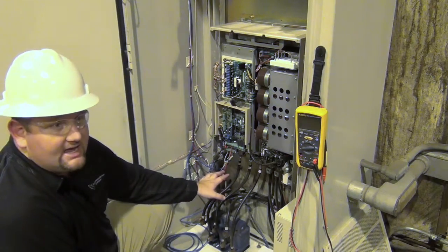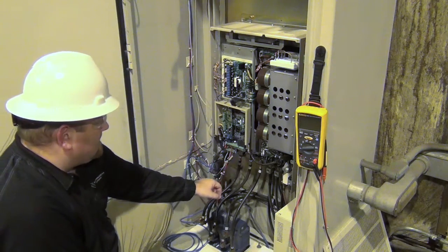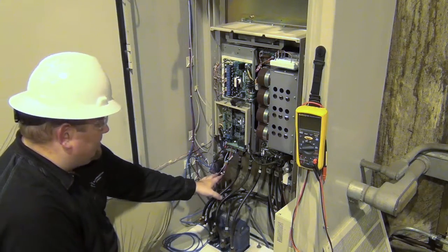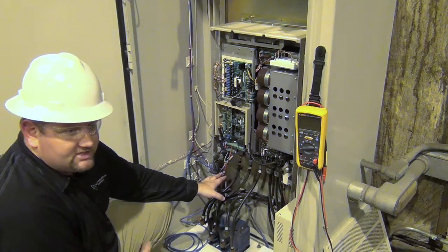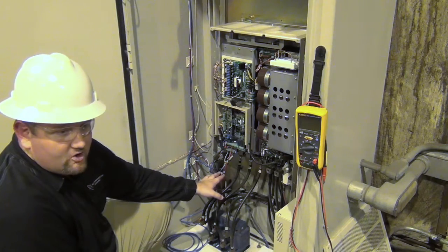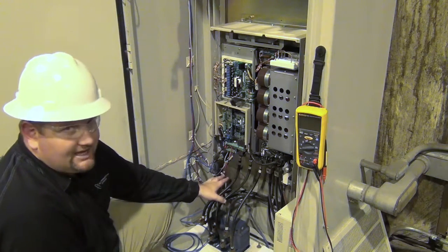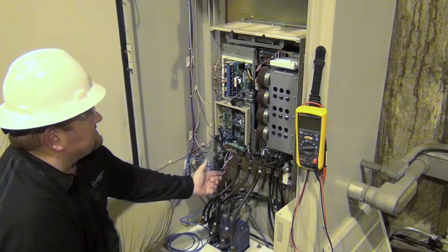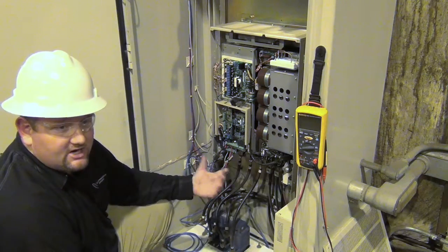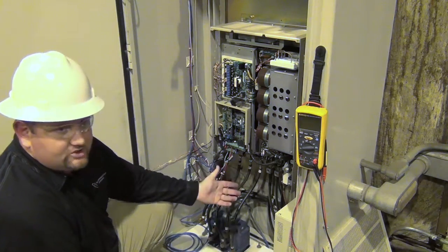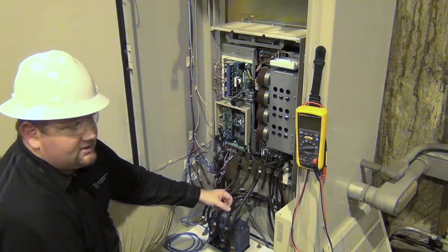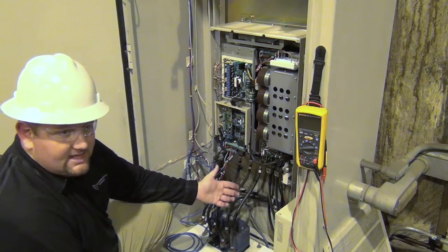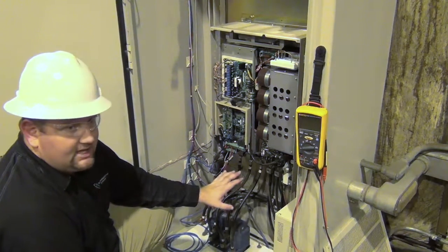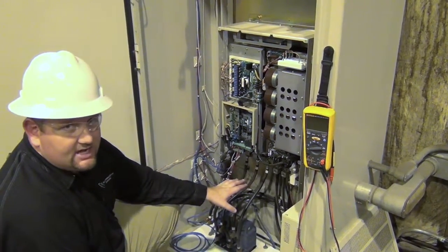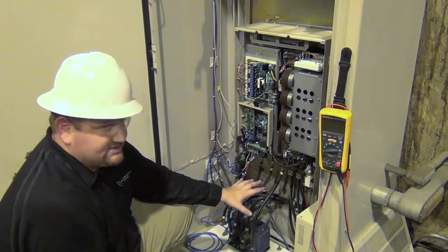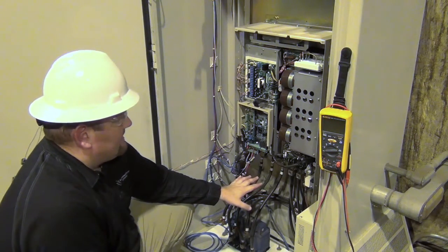And then on the input side, if you do line to line, you may also likely find two of them would also maybe show as a really low resistance or potentially appear as a short, 0.5 ohm or less. And again, generally what that'll be is somewhere ahead of the drive, there's a tapped off control power transformer. So again, a transformer will present just like a motor, and if you do an ohm reading line to line, it's okay to get a very low reading. That's not abnormal. If you ever get a reading line to ground that indicates a connection on input or output, that should be something that definitely warrants further examination.